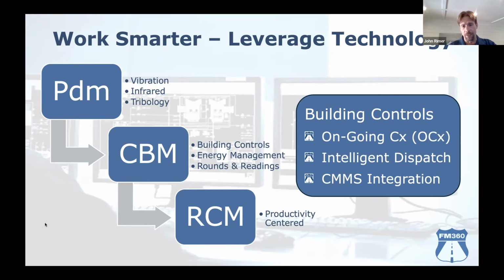Rounds and readings is another one I like to mention. We love our paper logs, but I cannot query and I cannot trend paper. So if I can take the data I'm getting from predictive maintenance, incorporate the data from my building control systems and maybe energy management systems, and now through my CMMS, I've got my technicians out there doing their daily rounds, once, twice, three times a day. Let's not keep that on paper. Let's put that directly into the CMMS where I'm capturing temperature, pressure, flow, you name it. That's going into the system. And then I can set up parameters on that as well.